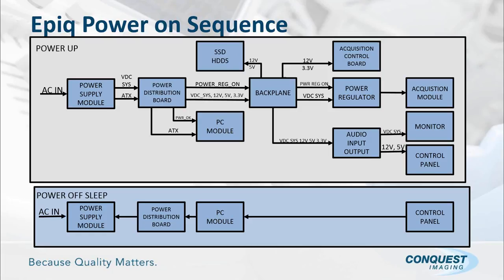At the same time, the 24 volts DC, the system DC, goes through the power distribution board, and you can see that it generates from there the 12 volts, 5 volts, and 3.3 volts going through the backplane with the power regulator on, and that power regulator on signal goes to the power regulator board, allowing the rest of the system to start powering on. So on the solid state hard drive and the regular hard drives, you have 12 and 5 volts delivered. On the acquisition control board, you have your 12 and your 3.3 logic voltages delivered. And then, as you can see, the audio input output gets your 24 volts as well as your 12 volts, 5 volts, and 3.3 volts.